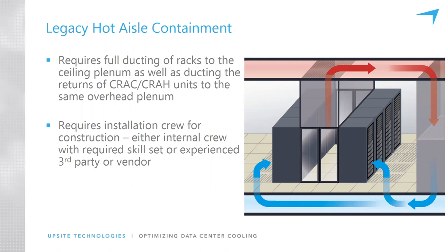Cold aisle containment is much more common. The advantages of hot aisle containment — which is the example we're looking at — is that if you're fully containing the hot air, then the rest of the room becomes cold and the placement of supply tiles is not as critical. The air is free to flow around the room and make its way to where it's needed. The room feels cool, airflow is managed more easily, and any leakage of conditioned air through the raised floor goes into the general space for cooling. Hot aisle containment tends to be more efficient because it tends to be done more effectively.